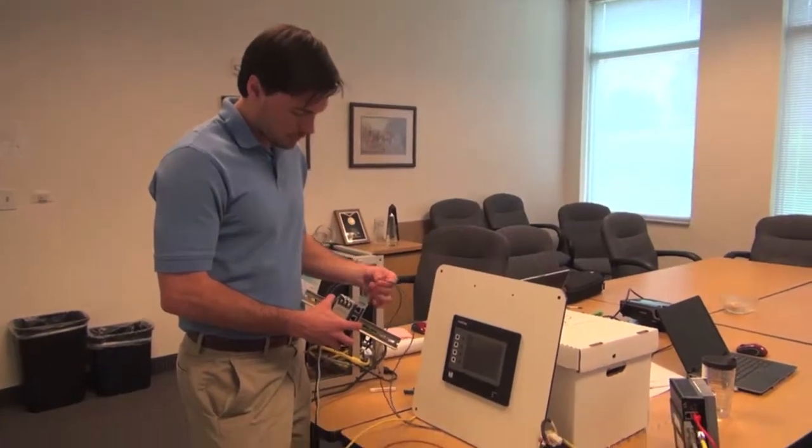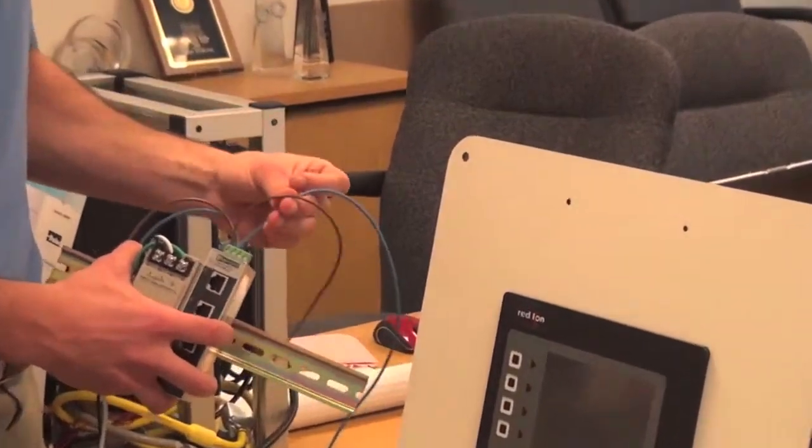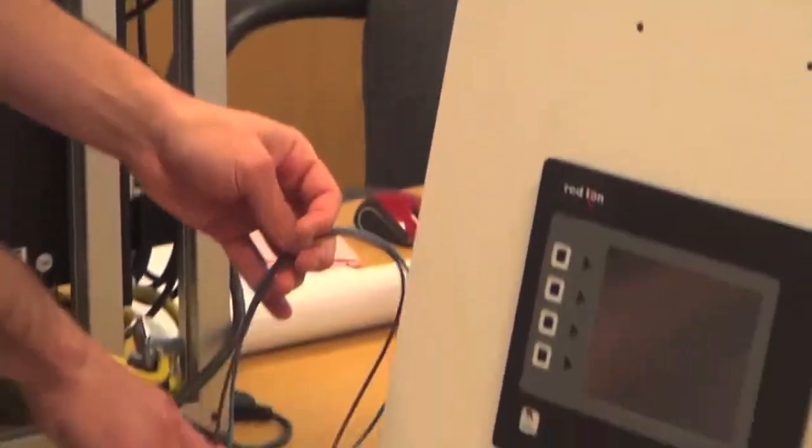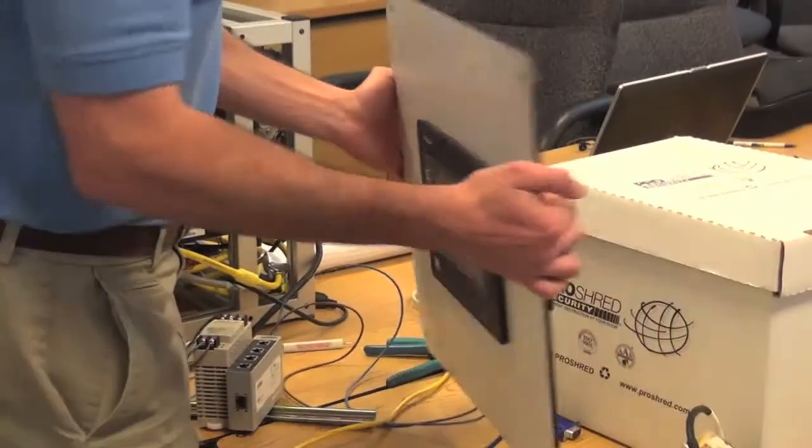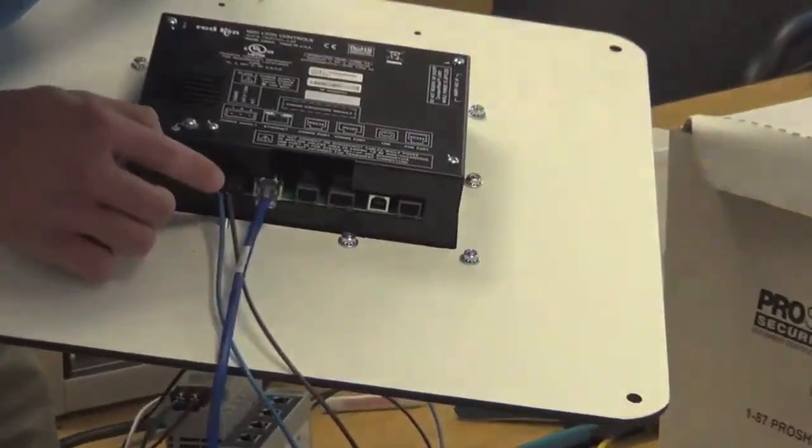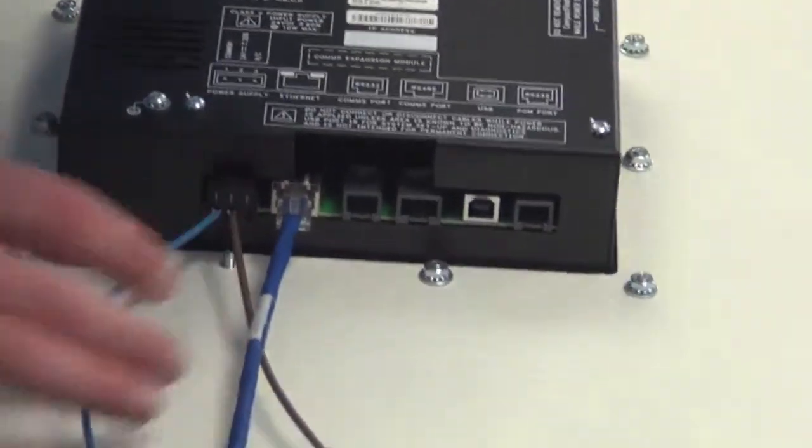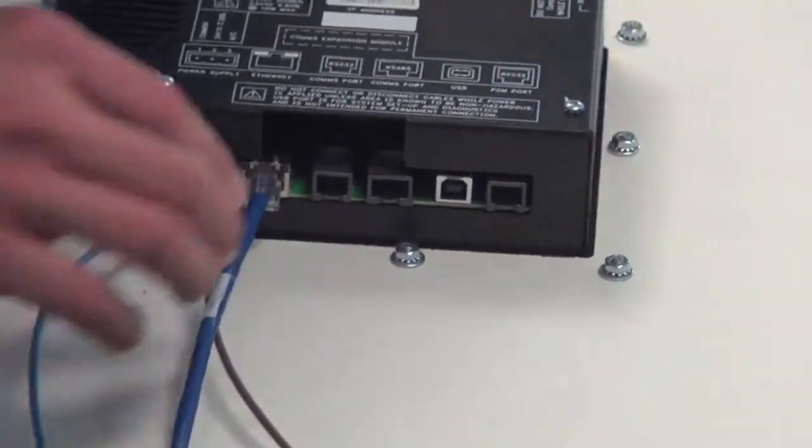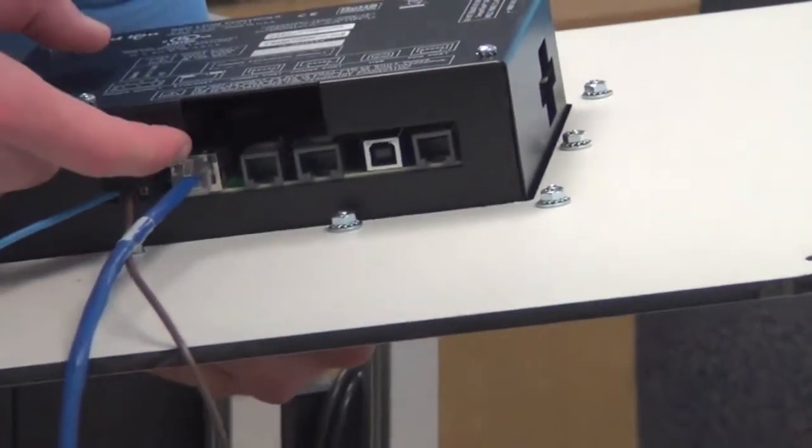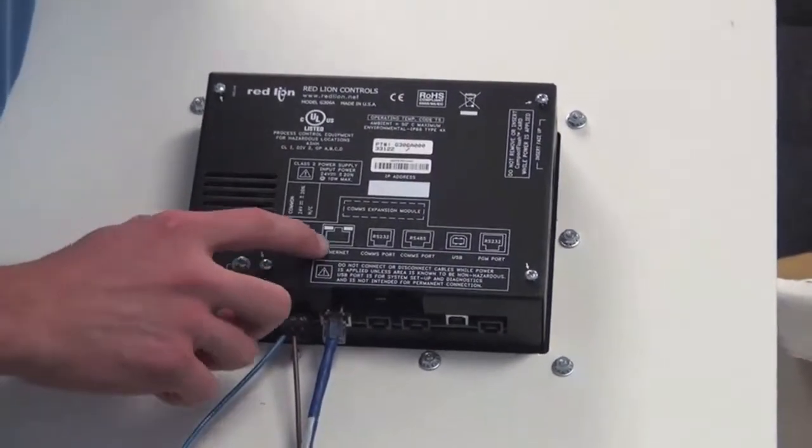Okay here we've jumpered the 24 volts DC, brown being positive voltage, blue being negative voltage, over to the Red Lion HMI on the back. Brown will go in pin 2 which is your positive voltage and blue will go into pin 1 which is your negative voltage. And here I've hooked up the ethernet switch into its ethernet port on the back of the Red Lion as you can see from the schematic.